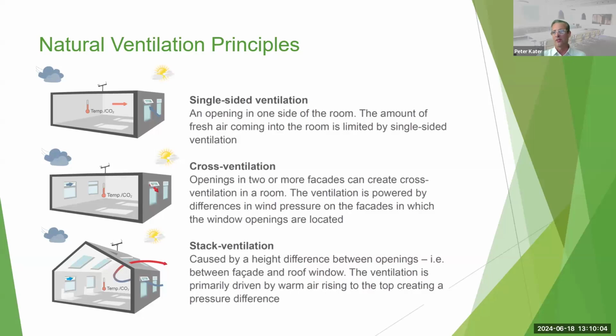The third category is called stack ventilation or stack effect, which utilizes the buoyancy force of warm air, which rises towards the upper level and draws in cooler air at the bottom. And this typically is used to drive air through the building in a vertical direction. These different modes can be used in combination with each other and optimized for the whole building.